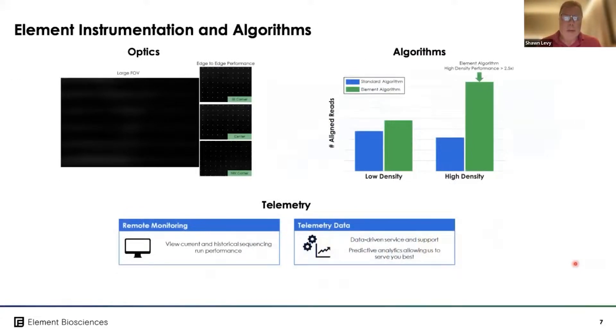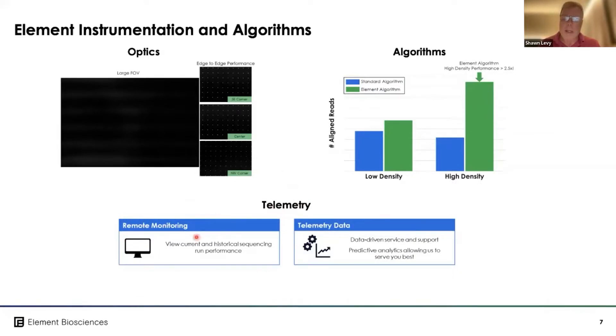One of the other differentiating features is a very large field of view in the optics, which enables very strong edge-to-edge performance. You can see the uniformity in these control flow cells. All algorithms for spot finding and high-density performance are developed in-house, allowing that flexibility out to 1.3 billion reads. Finally, the instrument has a strong telemetry system to allow remote monitoring of current and historical sequencing performance, as well as collection of telemetry data for record keeping and predictive analytics that allow us to observe when an instrument may need service proactively.